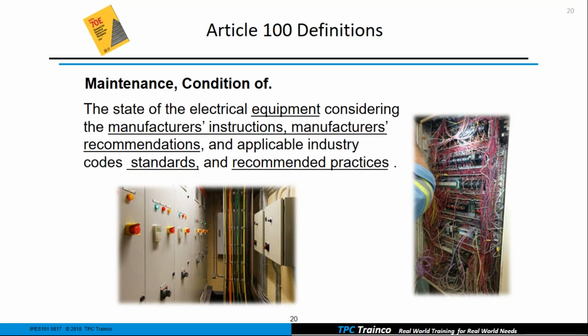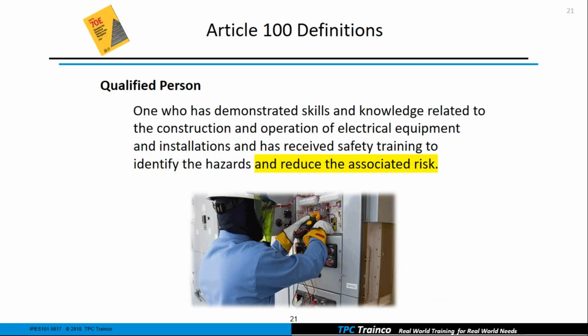So NFPA 70B, our publication for maintenance, would come into play there. And then recommended practices. So when we look at the condition of equipment, we've got to make sure that we're taking all that into consideration. We've got to make sure that the equipment has been maintained properly. They changed a little bit the definition of qualified person. It seems like every revision they play with this definition a little bit.